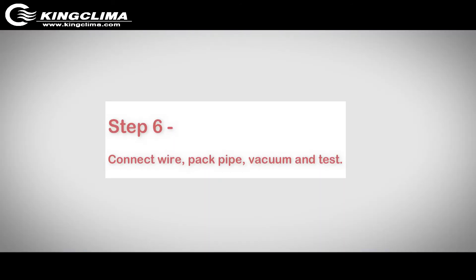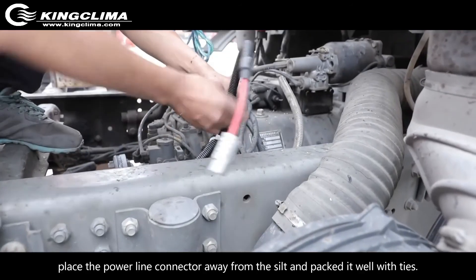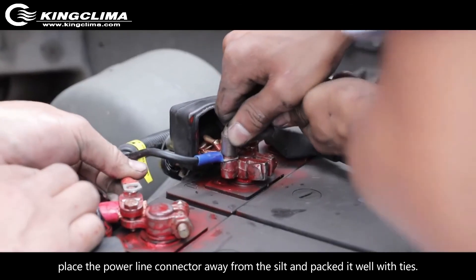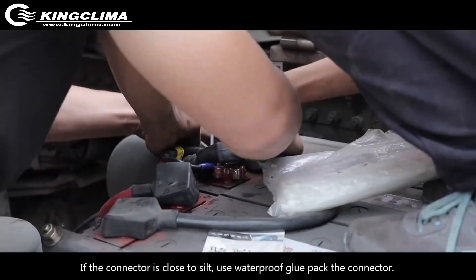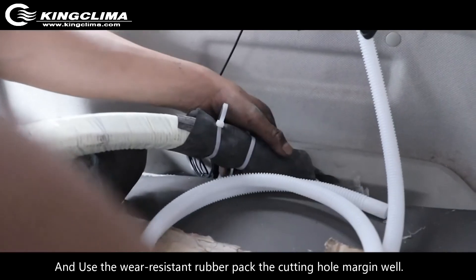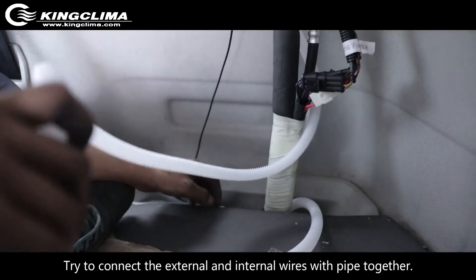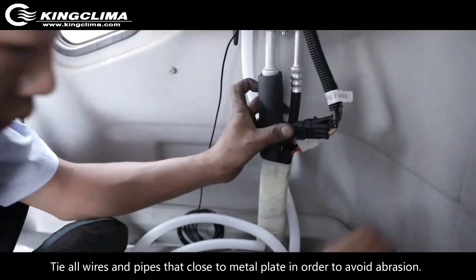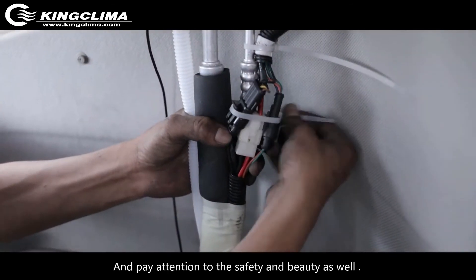Step 6: Connect the wire, pack pipe, vacuum, and test. Connect the condenser power line and storage battery. Place the power line connector away from silt and pack it well with ties. If the connector is close to silt, use waterproof glue to pack the connector and use wear-resistant rubber to pack the cutting hole margin. Try to connect the external and internal wires with pipe together. Tie all wires in the pipes close to the metal plate to avoid abrasion, and pay attention to safety and appearance.